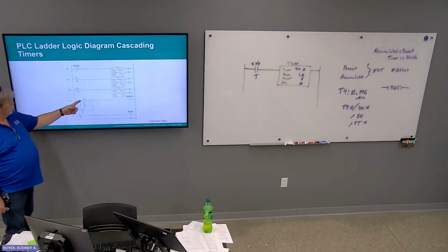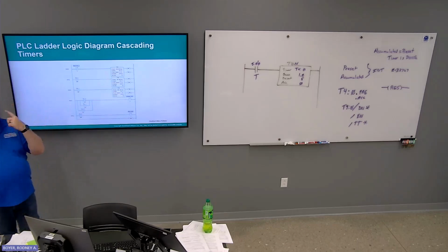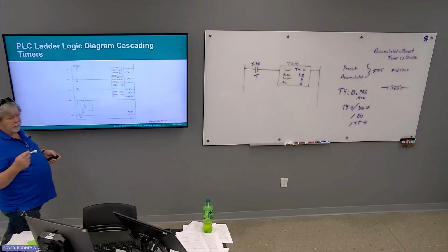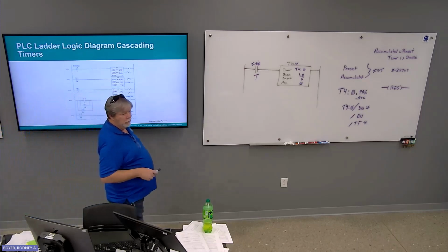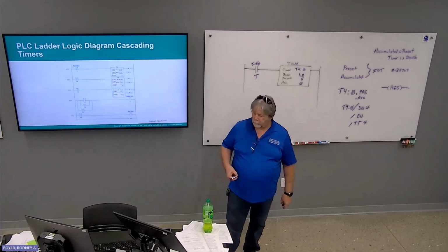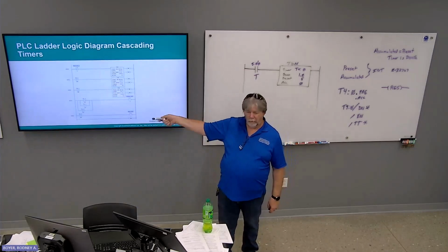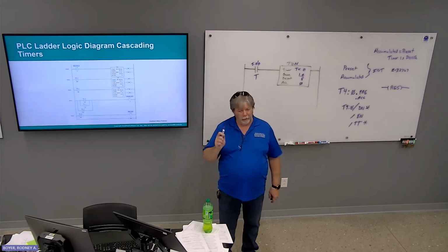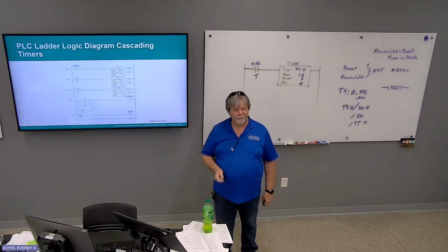This also works, but it takes more time for your program to scan that logic, because of the way it branches. It adds more clock cycles to the scan. It's a nested branch. Don't ever do that. Even though I've said that, none of you are going to pay attention, and you're all going to do it at least once.